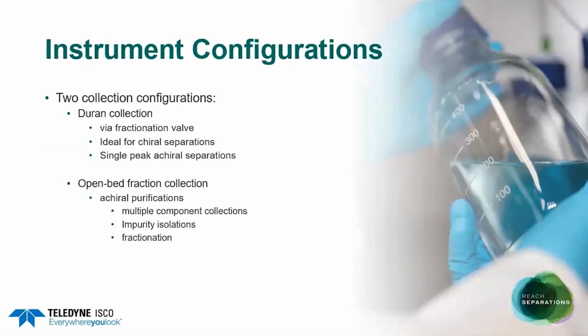If we move on to the configuration options we have on the ACCQPrep SFC, we have two collection configurations. The first one is collection into a drum via a fraction valve, which is similar to the slides we saw earlier, and is also similar to the other configurations we have on other systems in our labs. Now, this setup is ideally suited to doing chiral separations or single peak achiral separations. The second option we have is a collection into an open bed fraction collector. This is the option that will facilitate more achiral separations by SFC, particularly if we're collecting multiple components, being able to collect impurities into individual fractions or performing fractionation experiments.